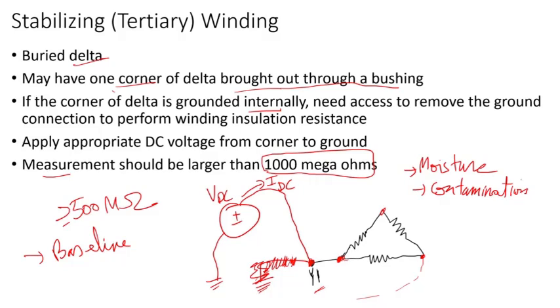To avoid all these issues, all you need to do is specify that one corner of the stabilizing winding or buried delta be brought out through a bushing, then ground that bushing. All you need to do is remove that jumper wire or bus bar, and now you can perform the test easily without opening the cover or draining oil. You don't have to do anything - just remove that conductor that connects the corner bushing to ground.